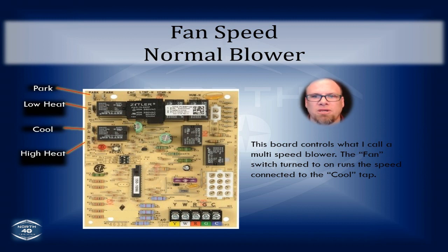One thing that you'll find out once you start actually checking your blower speeds is that your high heat and your cool speed will usually be very, very close to the same speed, and oftentimes will be the same speed. It's not the traditional way we used to do things. Traditionally, high was always cooling, low was always heating. Now they're pretty close to the same in most applications, and that's because nowadays we're doing load calculations, and load calculations are very precise on BTUs for loss and gain on both heating and cooling side, and so it's an interesting thing once you get to checking these things.